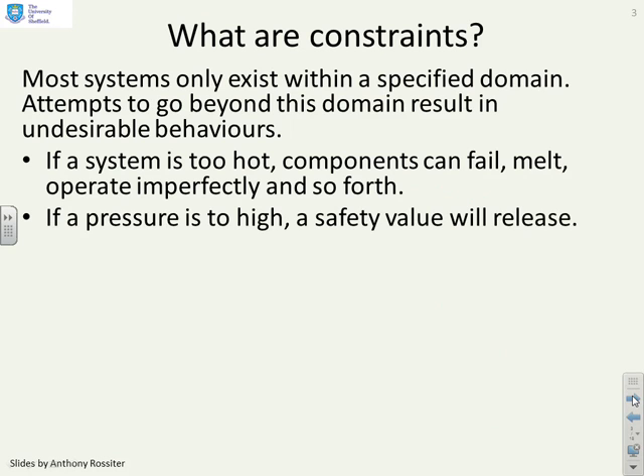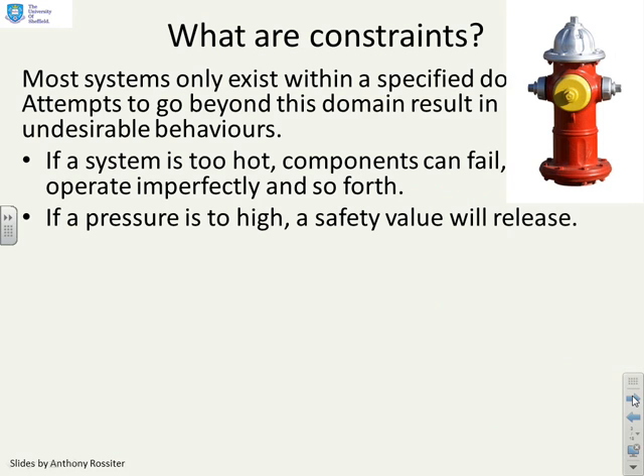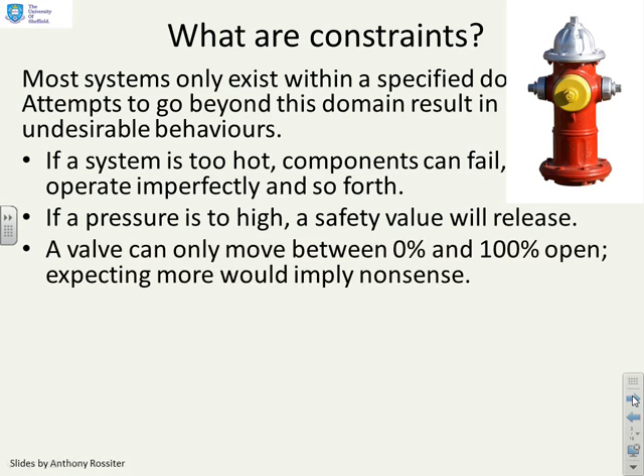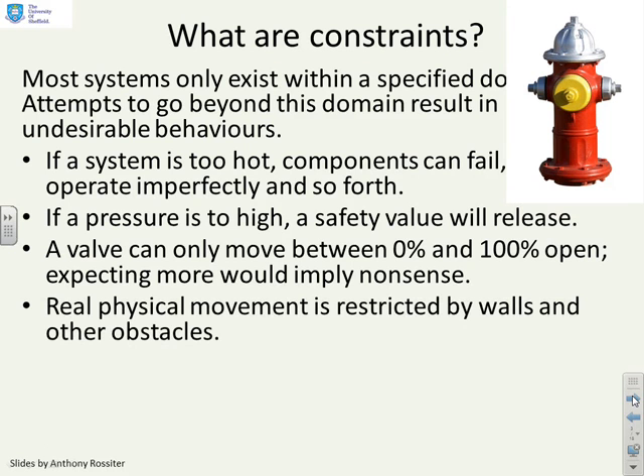If a pressure is too high then a safety valve may release and that could lose you lots of money's worth of valuable steam or something else. A valve can only move between 0% and 100% open. If your control law is asking for a negative percent or something beyond 100%, clearly it's asking for nonsense. Real physical movement is going to be restricted by walls and other obstacles, so there's no point having a control law which assumes that you can go beyond that.